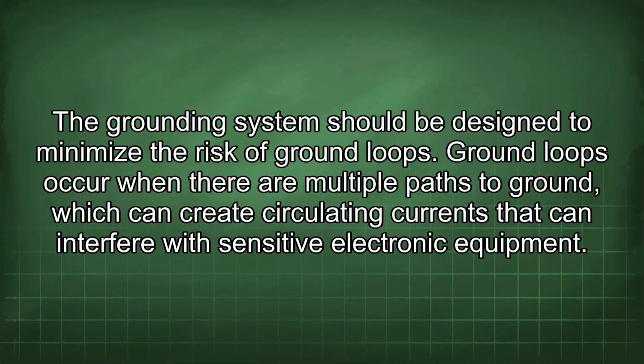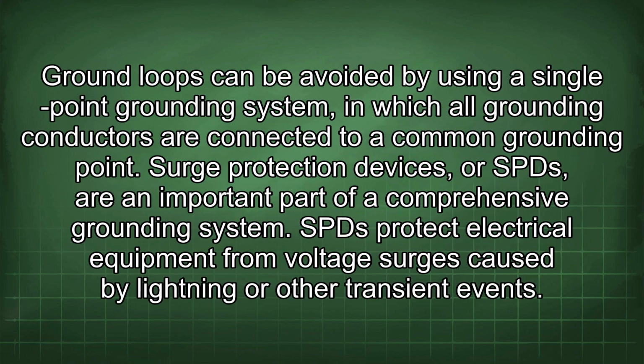The grounding system should be designed to minimize the risk of ground loops. Ground loops occur when there are multiple paths to ground, which can create circulating currents that can interfere with sensitive electronic equipment. Ground loops can be avoided by using a single-point grounding system, in which all grounding conductors are connected to a common grounding point.